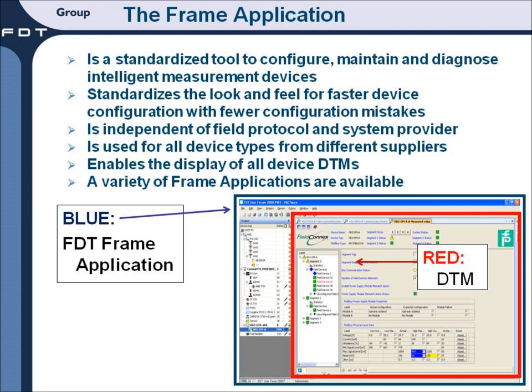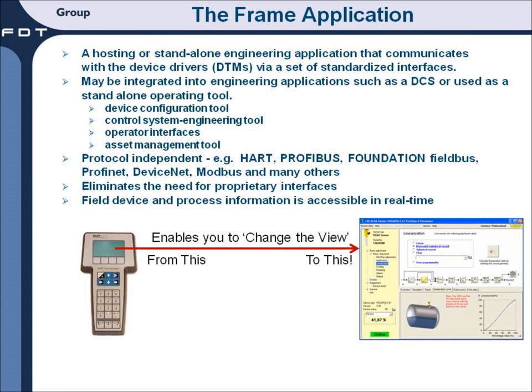Why review the device information using a frame application? One main reason is to quickly look for problems with the device or the process. Similar to the check engine light in your car, the diagnostic information in your smart device can provide an overview of the condition of your device. This can provide early notification of a potential problem with a critical control valve, flow meter, or other smart device. Frames can be embedded in device configuration software, control system engineering packages, operator consoles, or asset management tools. The frame application eliminates the need for multiple proprietary applications.